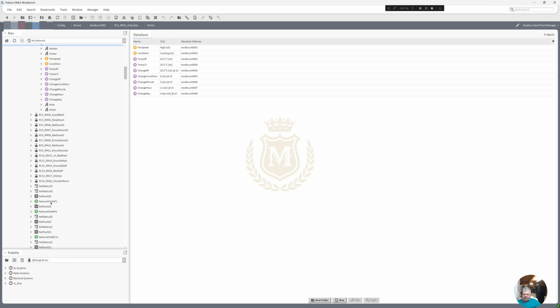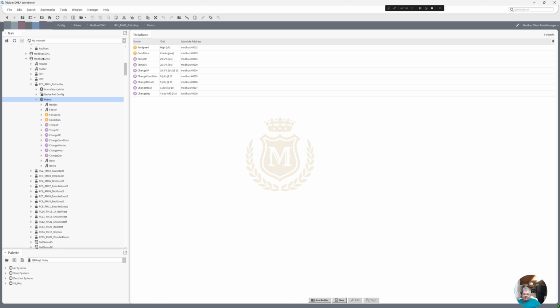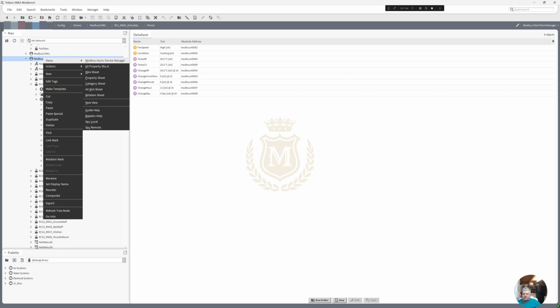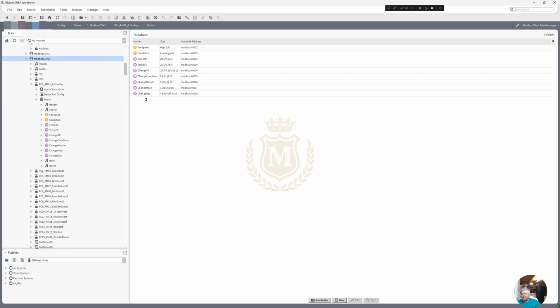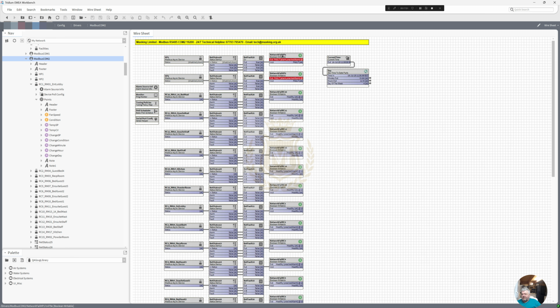We've also got some alarms here. If I right click this, views and wire sheet, that should put us into these alarms here. See these network, well, they haven't failed, we just don't have anything on heat pump 1 and heat pump 2, as I previously said. And then of course, if any of these network fails, I will get an alarm.